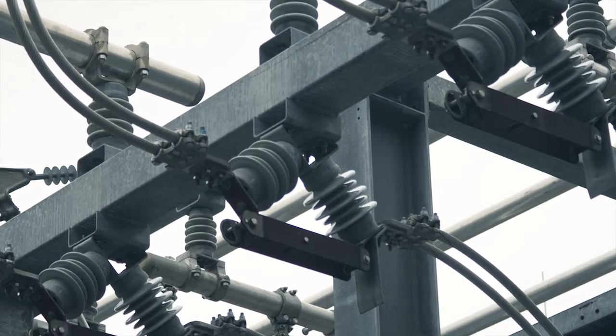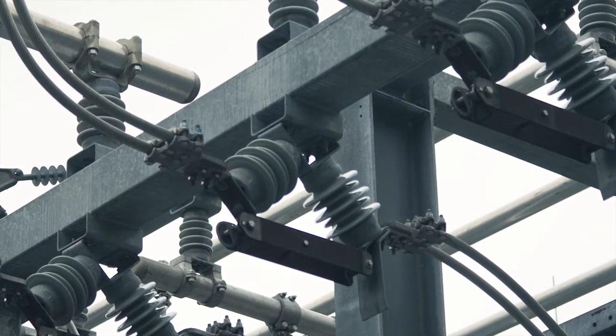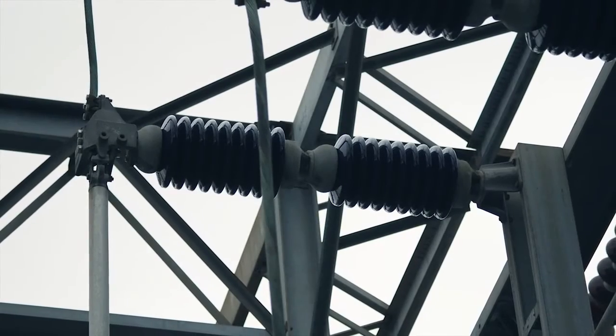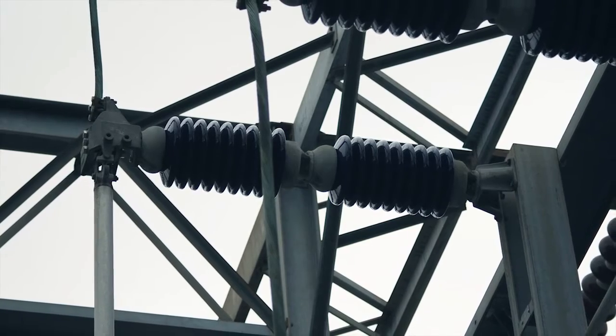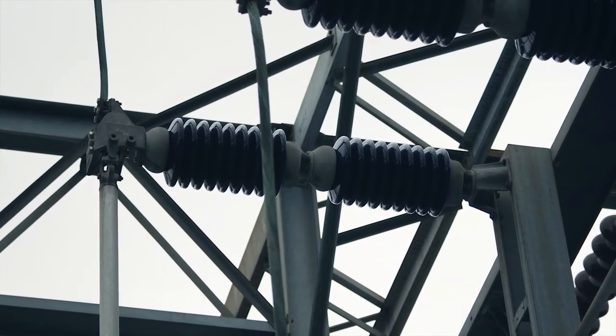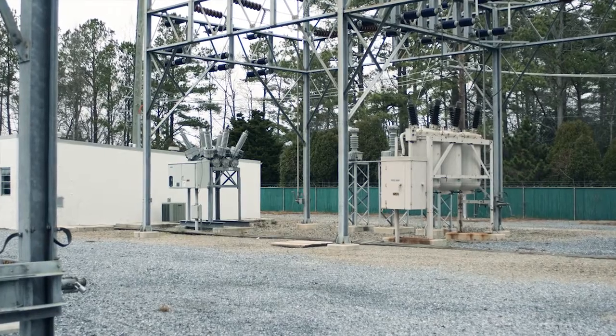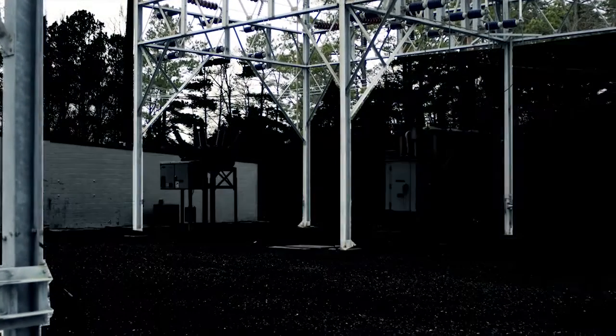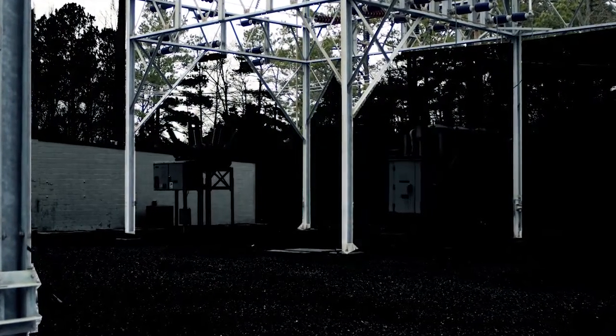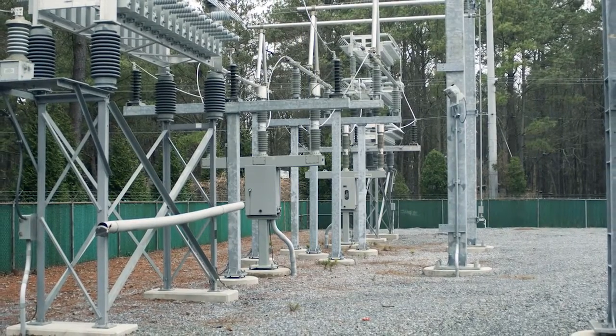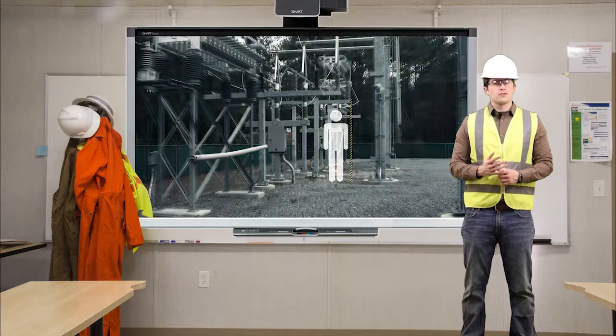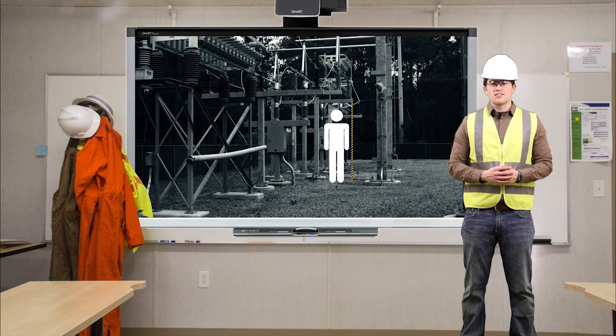Insulators prevent the flow of electric current and support the conductors. Insulators also help keep the conductors separated from structures, poles, and other equipment. Structures support the conductors and insulators. Structures also help keep most conductors elevated and out of reach of personnel on the ground. Be aware of substations with low conductors that could still be within reach.